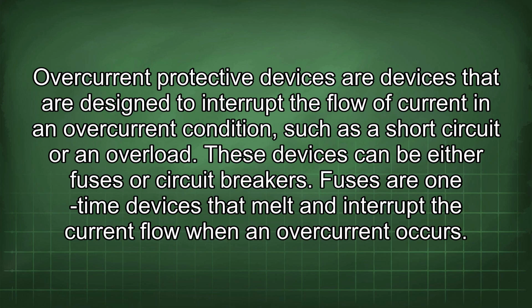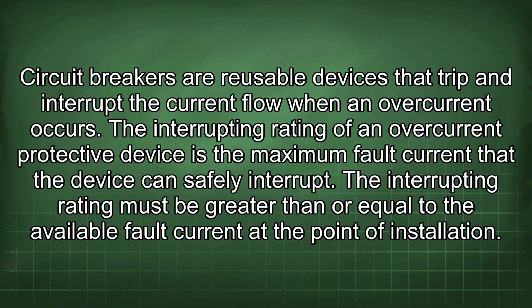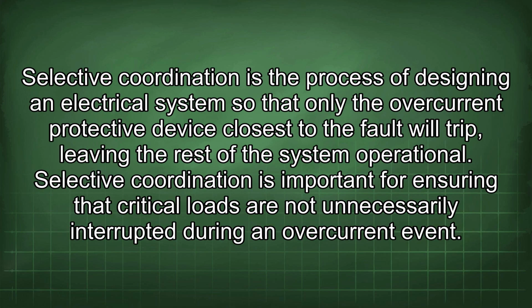Fuses are one-time devices that melt and interrupt the current flow when an overcurrent occurs. Circuit breakers are reusable devices that trip and interrupt the current flow when an overcurrent occurs. The interrupting rating of an overcurrent protective device is the maximum fault current that the device can safely interrupt. The interrupting rating must be greater than or equal to the available fault current at the point of installation. Selective coordination is the process of designing an electrical system so that only the overcurrent protective device closest to the fault will trip, leaving the rest of the system operational. Selective coordination is important for ensuring that critical loads are not unnecessarily interrupted during an overcurrent event.